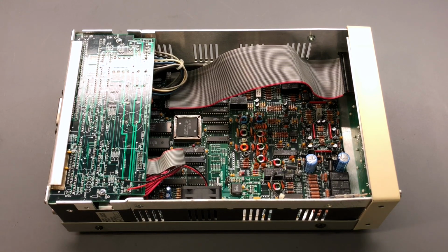Now, over time, things can age, and one of the things that can certainly age is the crystal oscillator, okay? So Stanford Research Systems, particularly in their service manual, they mention that the one cal byte that you will probably need to adjust over time is the calibration factor for the crystal oscillator. And we did see that the frequency was off by a little bit, okay?